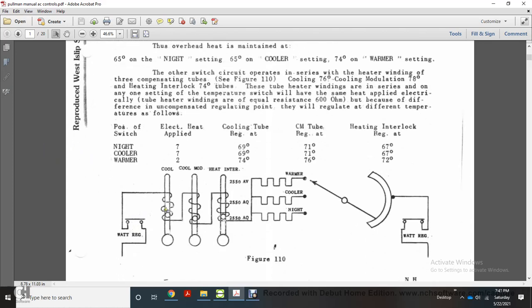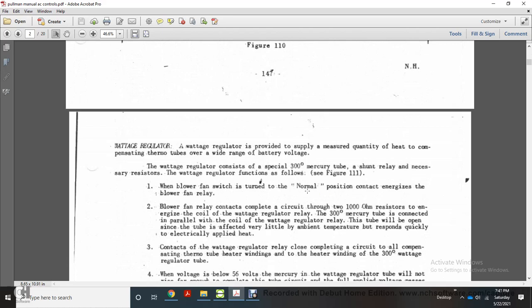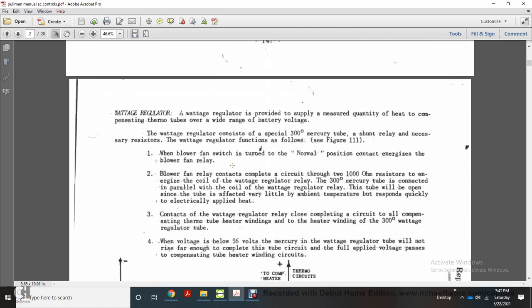The watt regulator is provided to supply a measured quantity of heat to the compensating thermo tubes over a wide range of battery voltage. The watt regulator consists of a special 300-degree mercury tube, a shunt relay, and necessary resistors. When the blower fan switch is turned to the normal position, the contact energizes the blower fan relay. The blower fan relay contacts complete a circuit through two 1000-ohm resistors, energizing the coil of the wattage regulator relay. This tube will open since it is affected very little by temperature and responds quickly to the applied electrical heat.